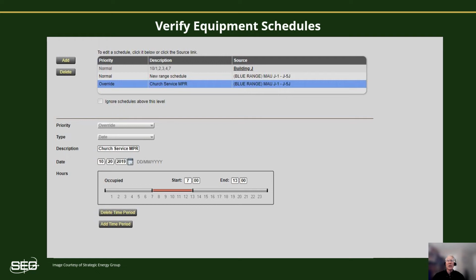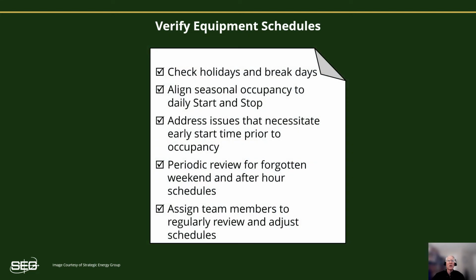Some buildings see occasional need to temporarily change the standard operating schedules due to a special event, meeting, or other activities. Whatever the reason, when setting up equipment schedules for temporary events, do not use the weekly scheduler. They're likely to be forgotten. Most building automation systems have a form of temporary event scheduler, and this is the tool to use for these occasions, as it's designed to execute once for a specific date and period of time, and then go back to the normal schedule. Now, since managing these different modes of scheduling can be a bit complex, we also recommend assigning scheduling change responsibility, as well as scheduling access capability, to one primary operator and a backup person.